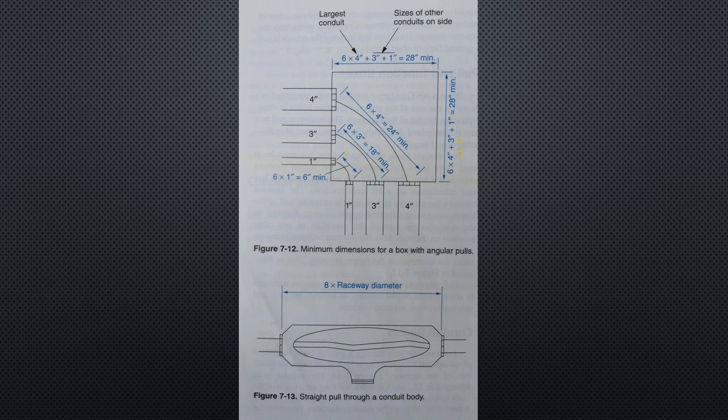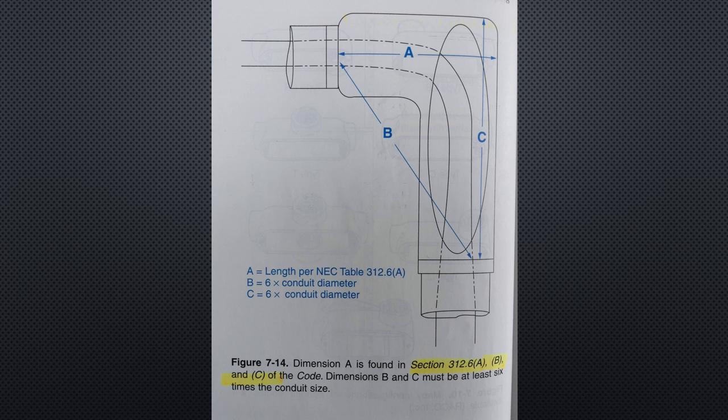Conduit bodies: for a straight pull through a conduit body, the length of the conduit must be at least eight times the diameter of the raceway. Figure 7-13 on the bottom. For angular pulls through LB, LL, and LR types, the long dimension of the body and the distance between raceway openings must be greater than six times the raceway diameter. However, the distance between the raceway entry and opposite wall along the short dimension can be less. The minimum distances are shown in section 312.6 A, B, and C of the code. For this, see Figure 7-14 on the screen.